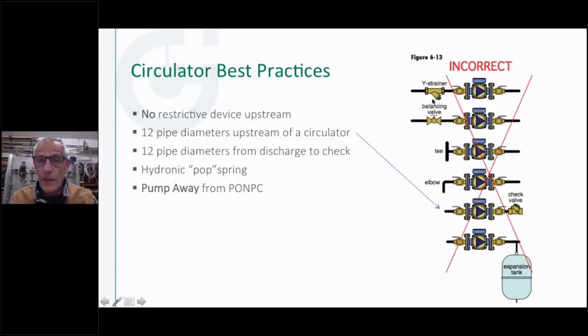And the other thing we always want to avoid with any circulator is putting a real flow restrictive device on the suction side of it. Certainly a Y strainer, which we know plugs up after time, and now you're going to starve that circulator for flow. So if there's a Y strainer, or ideally a dirt separator somewhere in the system, put it maybe on the inlet side of the boiler so we protect the boiler and the circulator. But again, we'd want at least 12 inches of pipe between any of these devices, if you've got a check valve or anything like that.